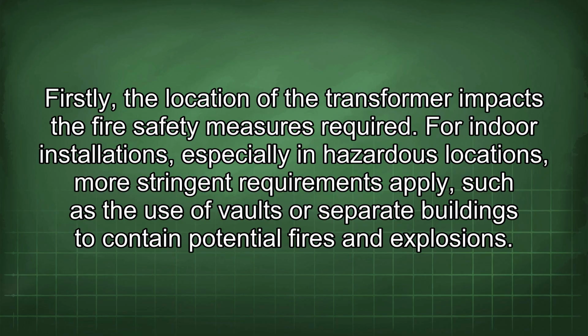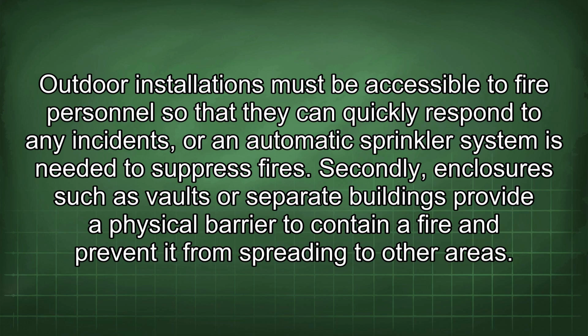Firstly, the location of the transformer impacts the fire safety measures required. For indoor installations, especially in hazardous locations, more stringent requirements apply, such as the use of vaults or separate buildings to contain potential fires and explosions. Outdoor installations must be accessible to fire personnel so that they can quickly respond to any incidents, or an automatic sprinkler system is needed to suppress fires.